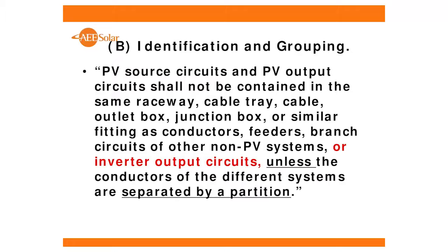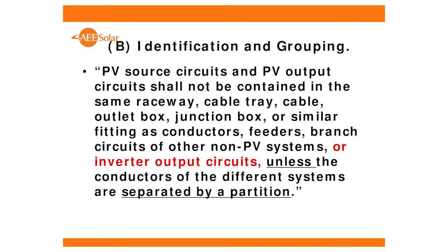Identification, so we talked a little bit about that. So this is where the 2014 code adds this statement here. This is the statement that kills us on grouping, which says that we're not allowed to group our source circuits with PV and with inverter output circuits. And that basically creates a real problem with trying to use the same gutter unless we have a partition, unless it's separated by a partition.